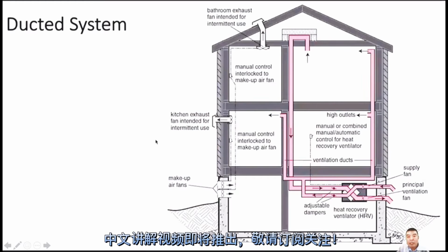Sometimes the HRV has five ports. The other port is a defrost port. We will talk about that later. This is a ducted system, for the new house. When they build a new house, they install the HRV there. For an older house, we cannot run the pipes like this. What we saw goes everywhere, like the kitchen and the washroom. But for an older house, if we install the HRV, we cannot run the pipe to the upper floor.